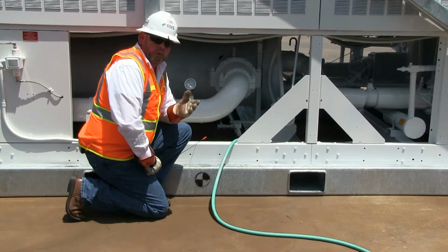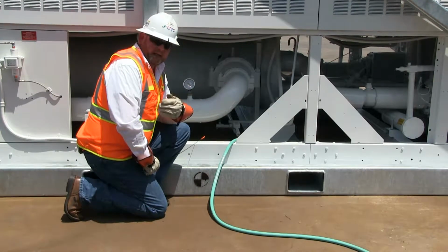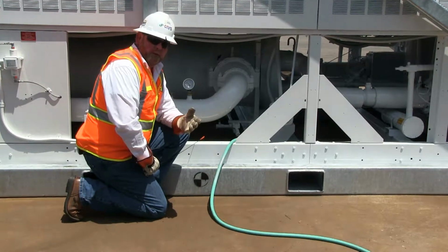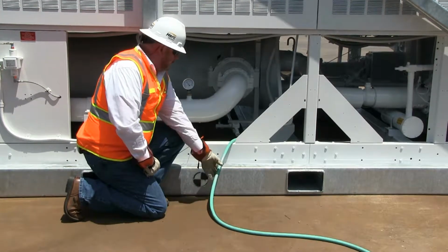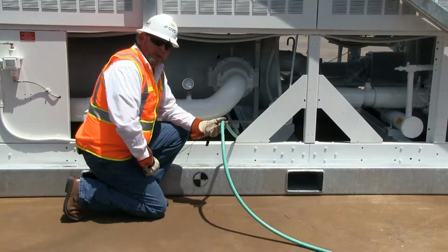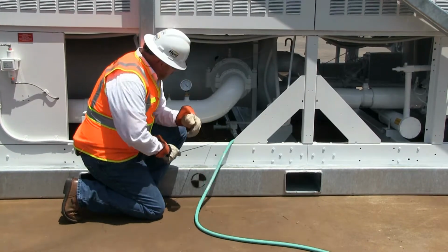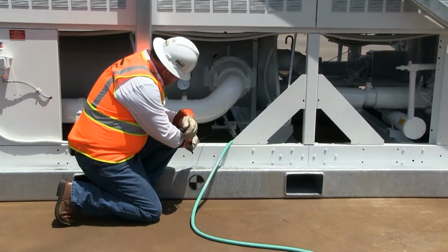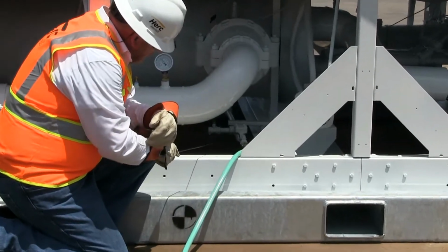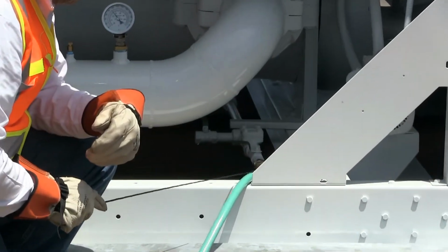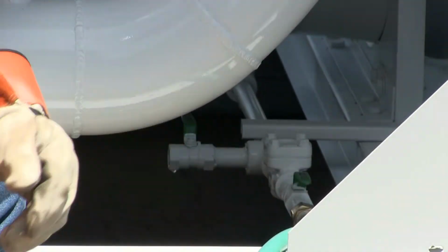Okay, we've hooked up our 4-inch quick connects on both the inlet and outlet of the chilled water flow. Now it's time for us to hook up our fill line. This is a 3/4-inch garden hose connection. We're going to hook it up to the valve here that has the check valve in line right there. This is a ball valve. Now we've got the water on here. We're simply going to turn the water on, and we'll be filling our system.